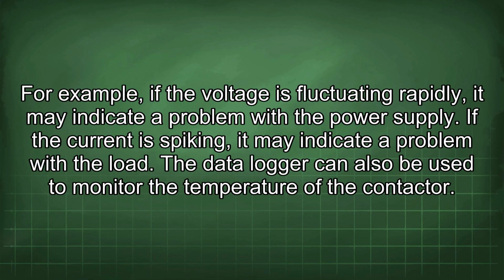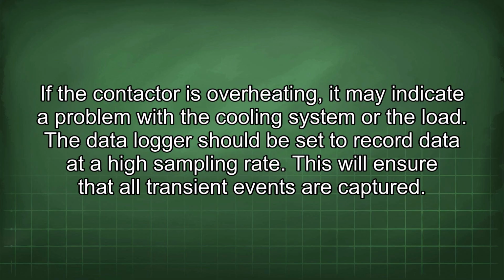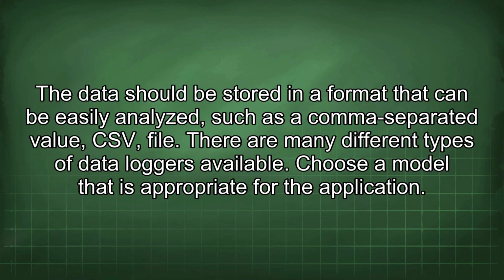For example, if the voltage is fluctuating rapidly, it may indicate a problem with the power supply. If the current is spiking, it may indicate a problem with the load. The data logger can also be used to monitor the temperature of the contactor. If the contactor is overheating, it may indicate a problem with the cooling system or the load. The data logger should be set to record data at a high sampling rate. This will ensure that all transient events are captured. The data should be stored in a format that can be easily analyzed, such as a comma-separated value (CSV) file.